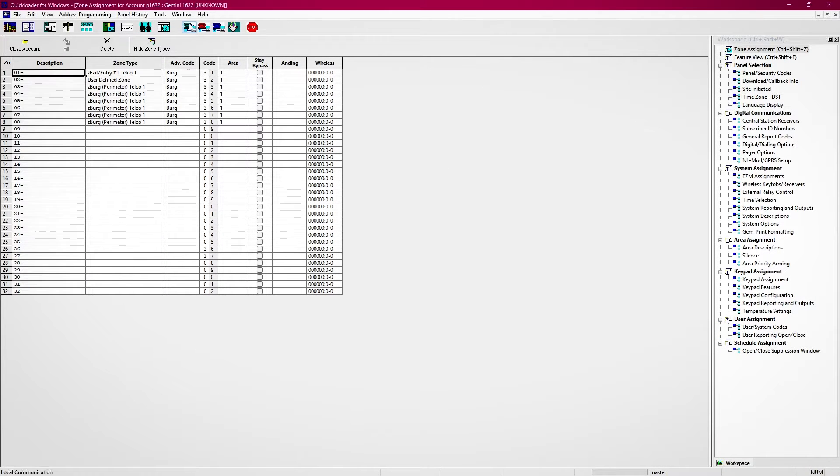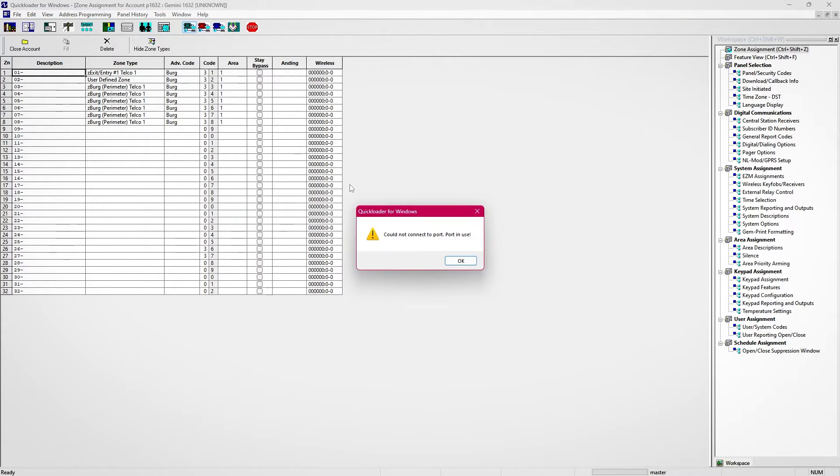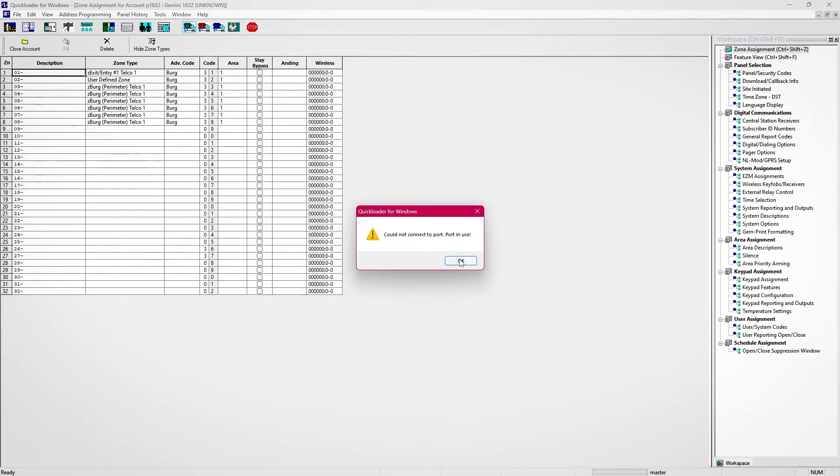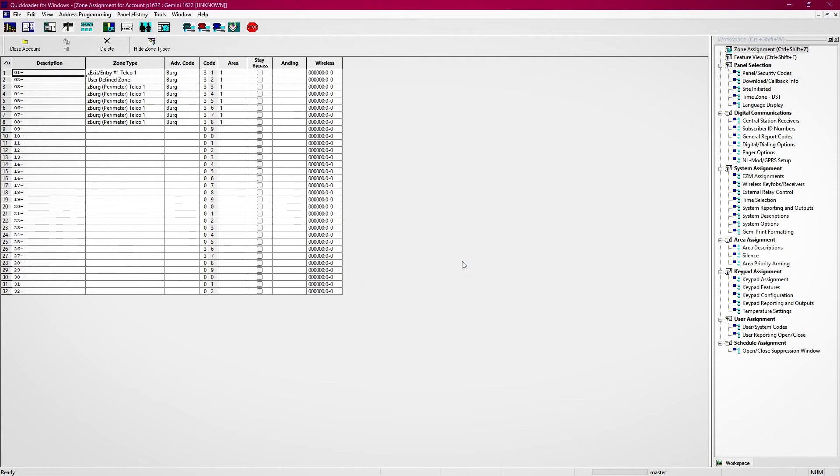The second most common issue you can have with connecting QuickLoader to a Gemini panel is when you get an error that says cannot connect to port, port in use. This is most often caused by having the wrong port number set in your modem settings.